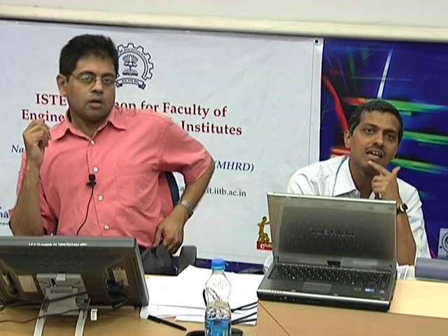In oil, the thermal boundary layer thickness is smaller compared to that of air. So, that itself is answering directly. Number one, actually, first of all, why we are using oil is not because of boundary layer thickness, but because its specific heat is very high. So its heat carrying capacity is very high, and that is the reason why we use oil. It is not directly related to boundary layer thickness; it is related to specific heat and heat carrying capacity. For a given mass flow rate, m Cp delta T is very high in case of oil compared to air, and even compared to water. Cp of air is 1050, and Cp of water is around 4180. I am sure Cp of oil is much more than 4180.